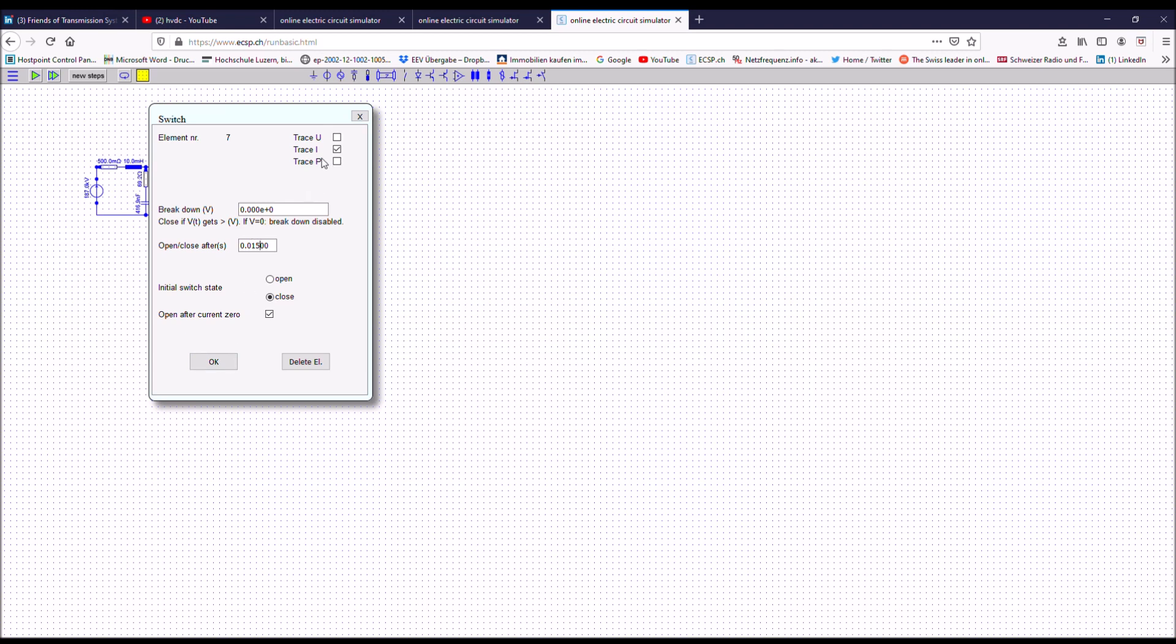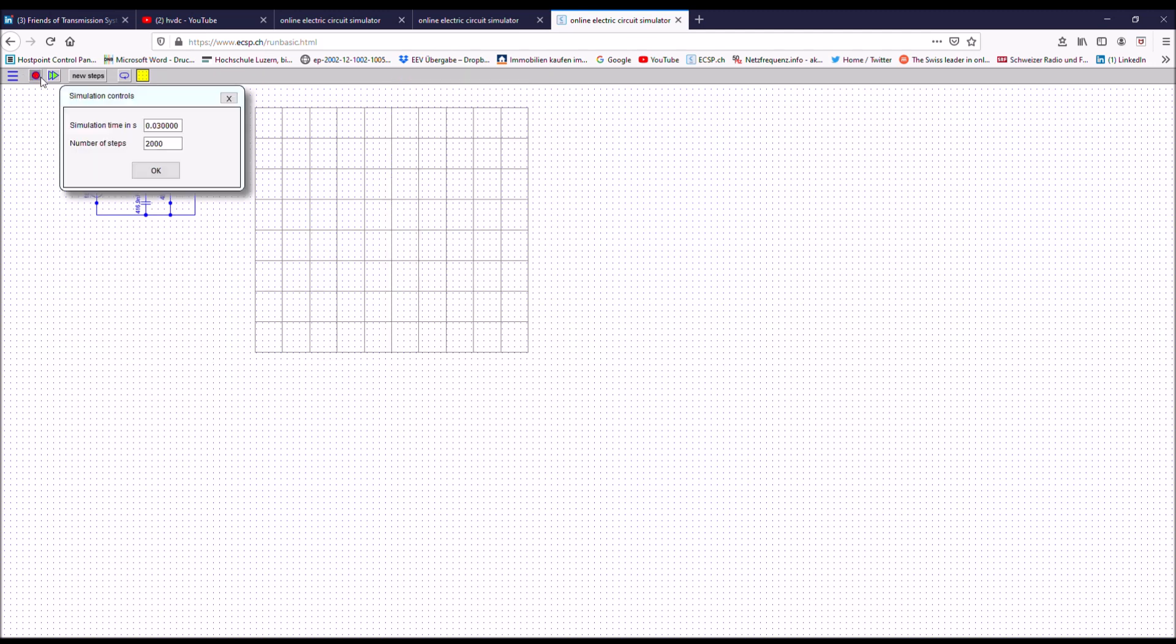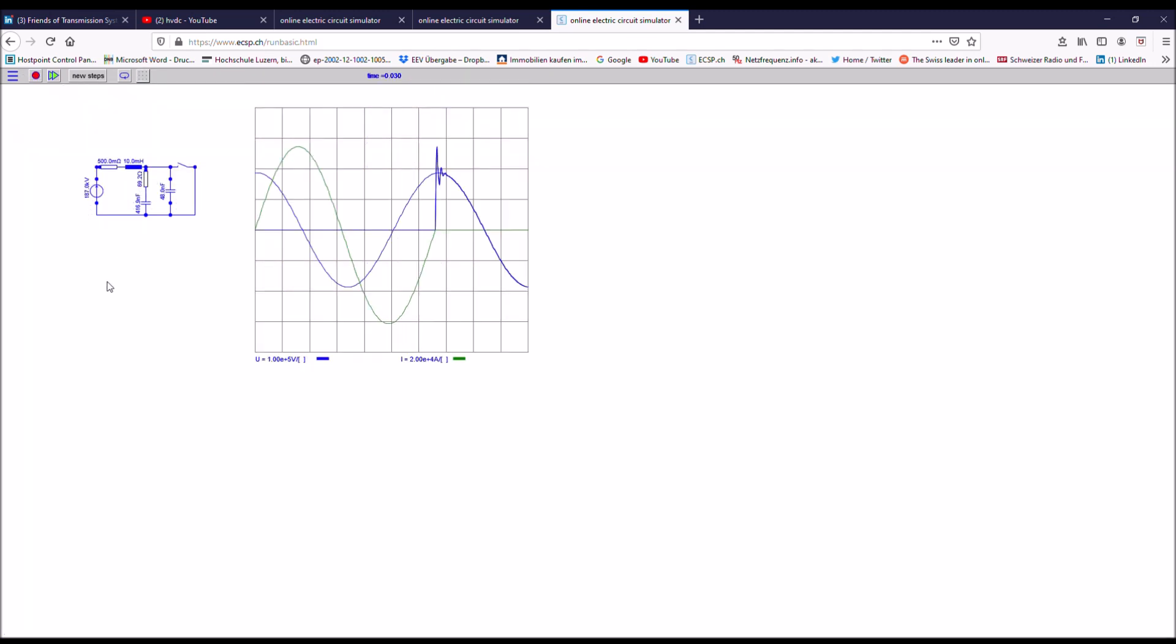I also want to see the voltage across the breaker. You see contact separation around about here and here the breaker is able to interrupt the current. And this is now the transient recovery voltage across the breaker. This is really stressing the breaker very much.